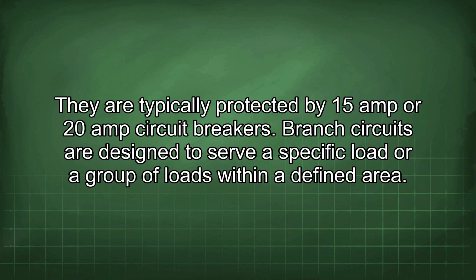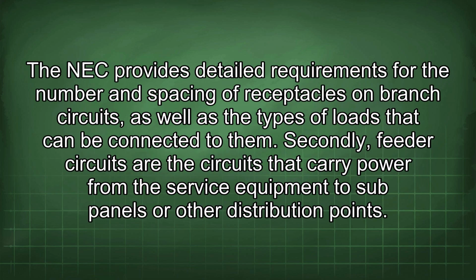Branch circuits are designed to serve a specific load or a group of loads within a defined area. The NEC provides detailed requirements for the number and spacing of receptacles on branch circuits, as well as the types of loads that can be connected to them.